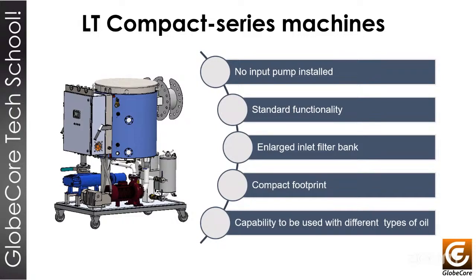Okay. At the same time, the capacity and functionality of these machines is not compromised by having no input pump installed. The inlet filter banks have been increased and enlarged. We know that if we don't have a pump at the inlet, we want to reduce the effort made by the vacuum pump for sucking the oil. That makes us enlarge the inlet filters of the machine, and we increase the capacity to retain contaminants in these filters. Due to the really good seals, filters, and filling system in the machines, this machine can also work with turbine, industrial, and natural ester oils, and every different type of oil.